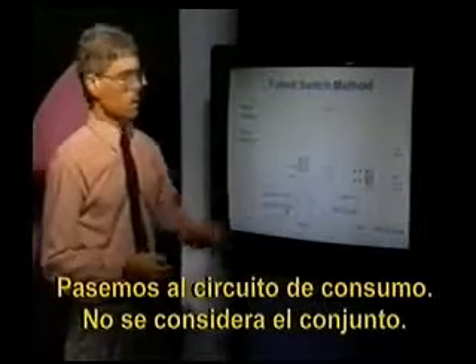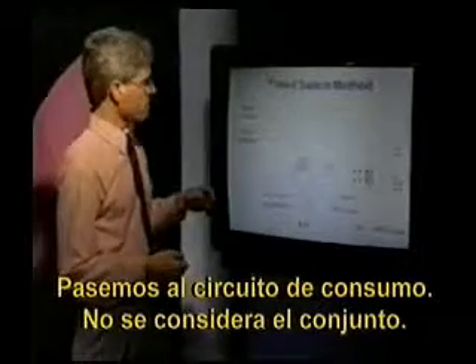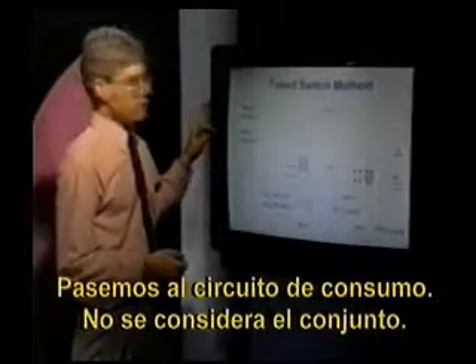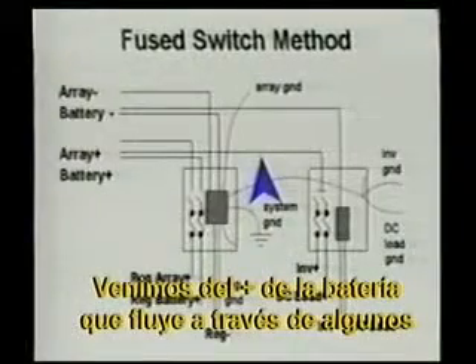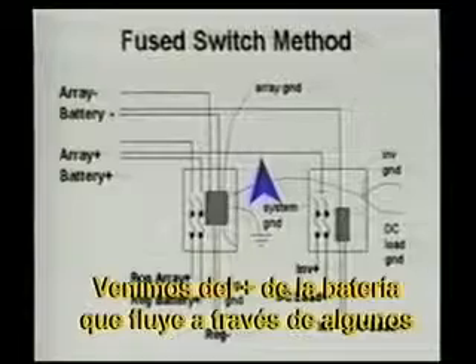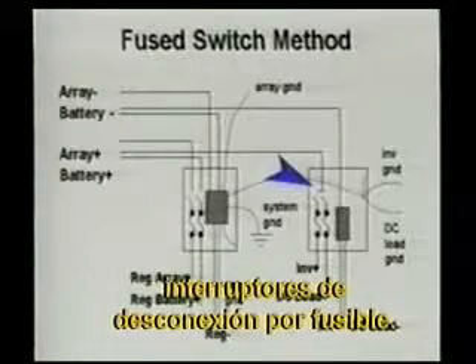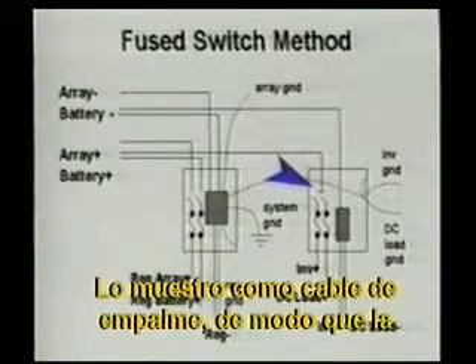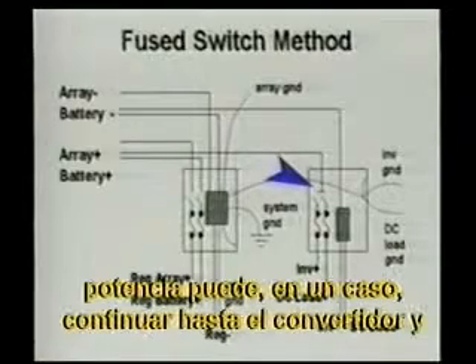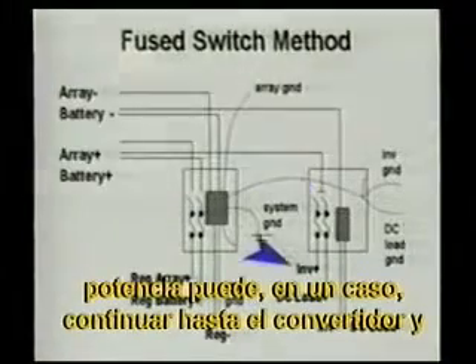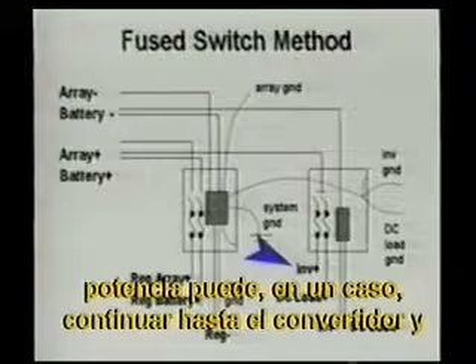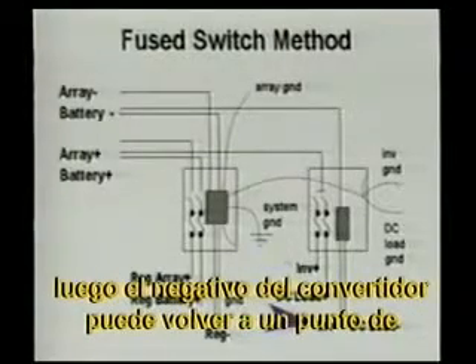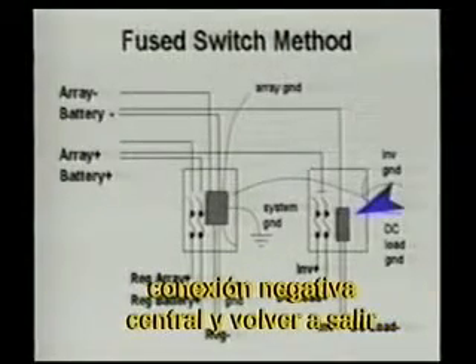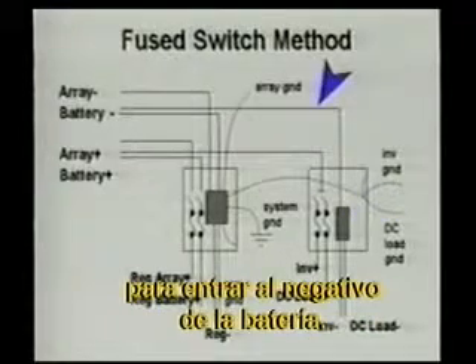Let's look at the load circuit now. We don't need the array considered. We come from battery plus, flowing in through some fused disconnect switches. I show it jumpered so that the power can, in one case, go on to my inverter, and then my inverter negative can come back into a central negative connection point and flow back out to my battery negative.